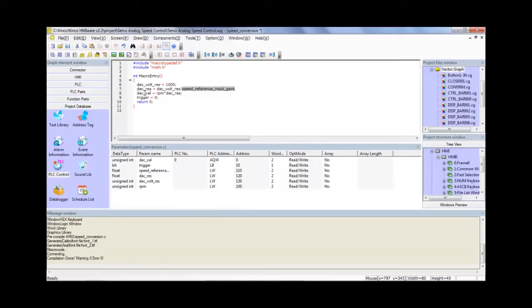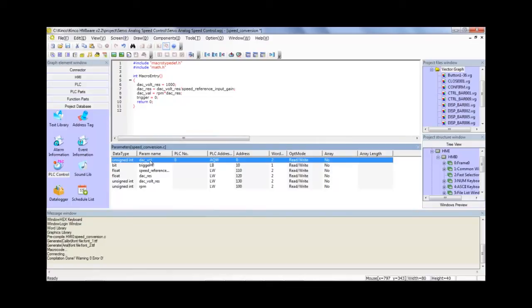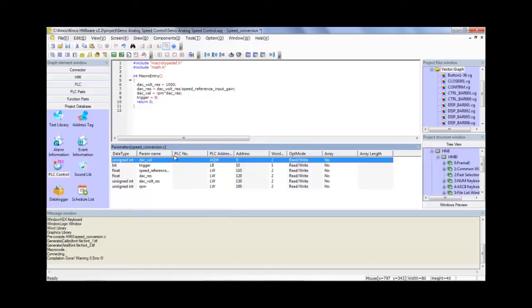So now you'll see that these variables have registers assigned to them. So the final output is going to be AQW0. The rest of these are just local bits and local words that live on the HMI and don't get transferred. The only thing that gets transferred to the PLC is this final DAC value right here.